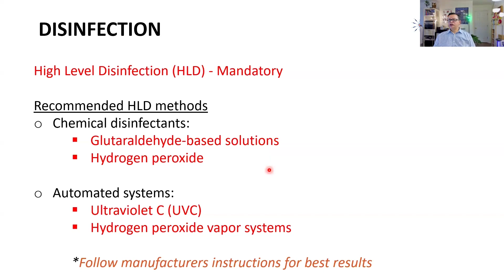And you must follow the instructions of your device manufacturer as well as the instructions for the system or the chemical that you're using, because they may say, dip the probe for 10 minutes in the solution. So you cannot bypass that. You must dip it for 10 minutes. You cannot do it for 1 minute and hope that it is disinfected. Even though we cover the probe with a sheath or a condom or something, we must do proper disinfection. We owe it to ourselves and to our patients. We do not want to transmit infection from one patient to the other.